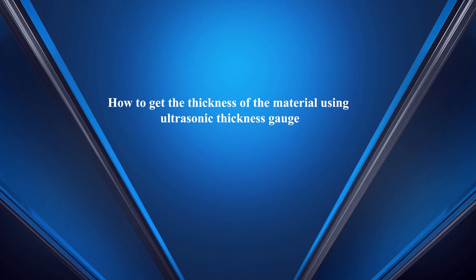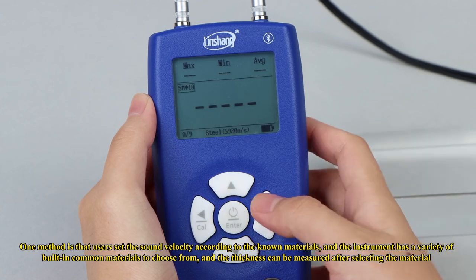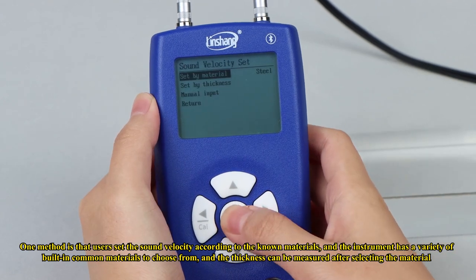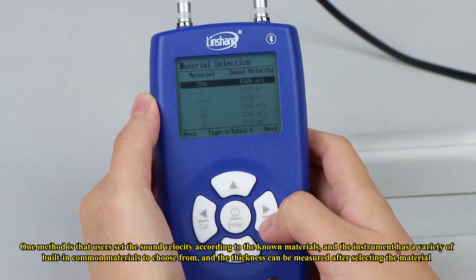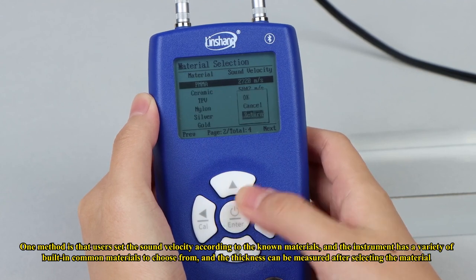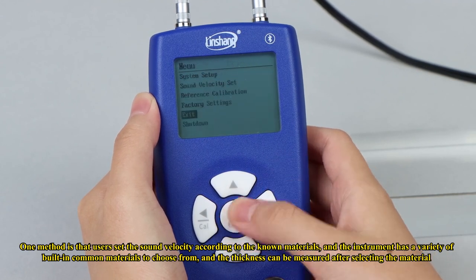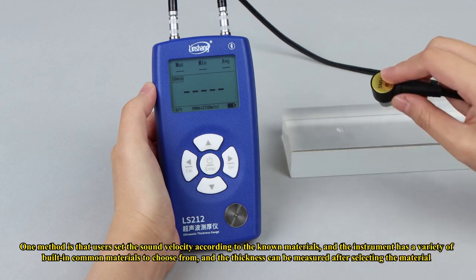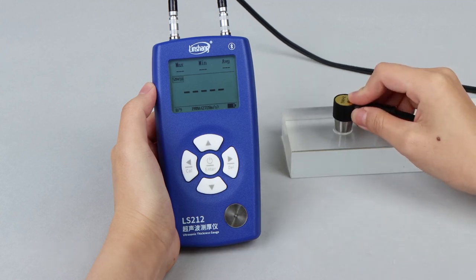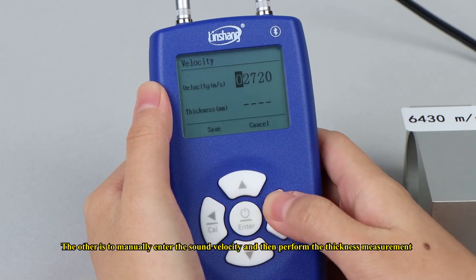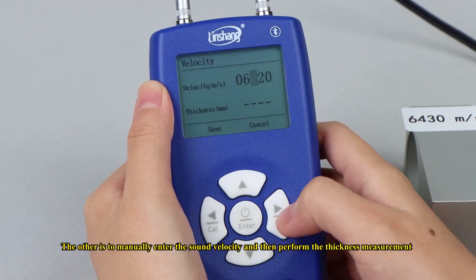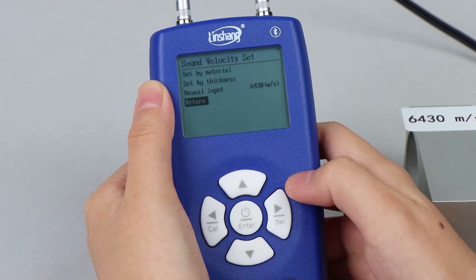How to get the thickness of the material using the ultrasonic thickness gauge. One method is that users set the sound velocity according to the known material, and the instrument has a variety of built-in common materials to choose from, and the thickness can be measured after selecting the material. The other is to manually enter the sound velocity and then perform the thickness measurement.